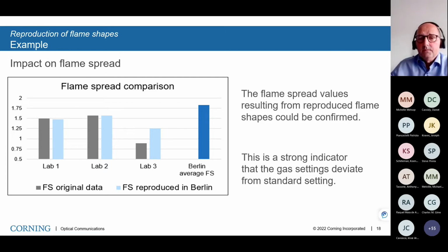This is one example where the correlation between a short flame and some failure in experimental parameter settings could be proven. The results also confirm that significant flame spread variation cannot be explained by variation of parameter setting in the gas mixture within the standard tolerance range.